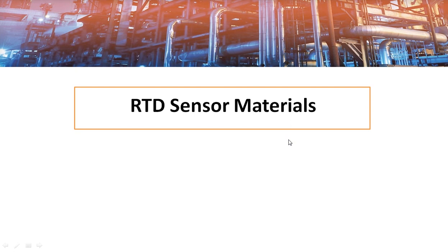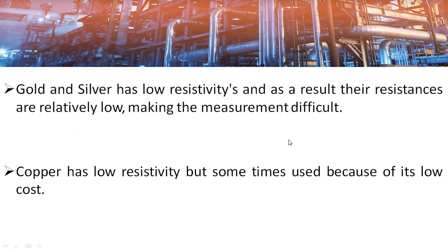The widely used metals for RTDs are platinum, nickel, and copper. There are other metals but they are not used because of their limitations. Gold and silver have low resistivity, meaning their change in resistance per unit temperature variation is low, making measurement difficult, and because of that these metals are not used for RTDs.